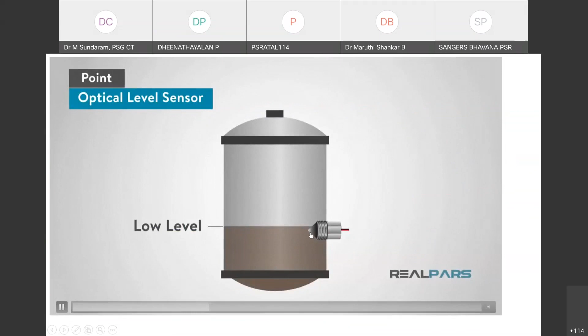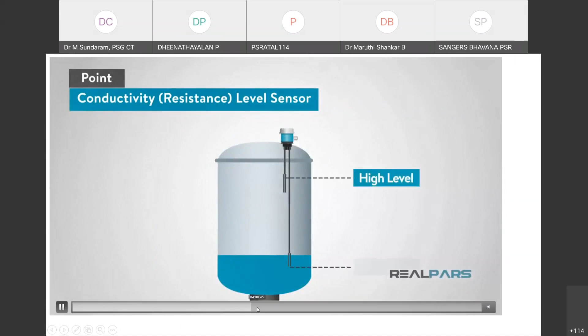Next one is the very low cost resistance type. See, at low level, when it gets filled and touches the top electrode, then the conductivity will make it act as a switch. So the conductivity resistance change in this is calibrated in the controller. So thereby the distance or the level or the fluid quantity can be indirectly calibrated. It has fewer parts and the cost is less, very easy to use. But again, it is invasive and only useful for conductive liquid. The probe will get eroded in a few years or days. But it can be used for anything.